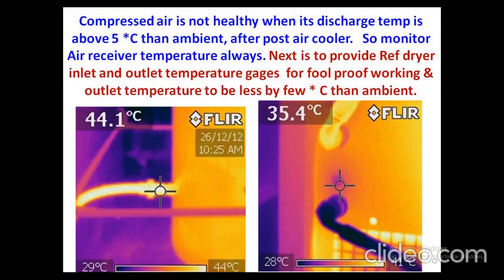Coming to the compressed air, it is healthy provided the air receiver temperature is controlled. If the ambient temperature is 40, the air receiver temperature has to be less than 45 only. 5 degrees is the maximum allowable. So you have to educate the mill as well as the OEMs and refrigeration dryer makers. They are supposed to have temperature gauges at the air receiver. Worldwide, you have not seen any air temperature gauge on the compressed air receiver.